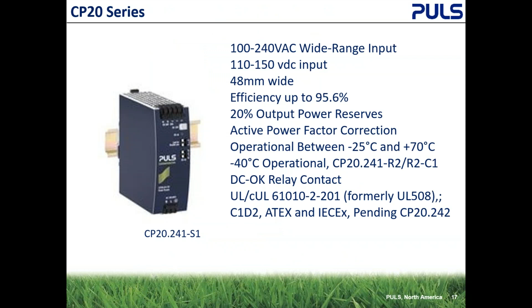Minus 40C operation for the redundancy units, DCOK contact, the same power, so 20 amp continuous, 24 amps minus 25 to 45C is 24 amps, and you can run it constantly. Again, when you get over 24 amps, you don't want to have a load greater than 20 amps just because of the heat buildup. We'll take the wide, extended range DC input, 110 to 150 volt, and it is only 48 millimeters wide.